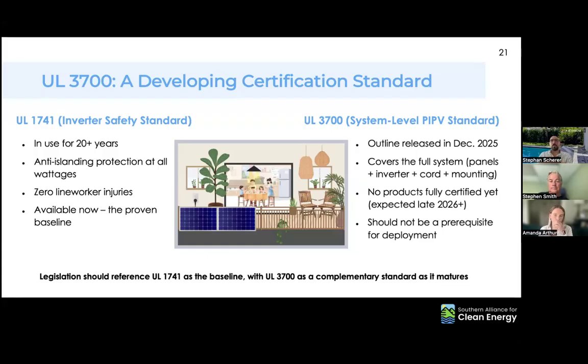In the meantime, as a draft certification, it tries to cover certain topics not covered by previous certifications. We've got UL 1741 for inverter safety, and UL 3741 for breaker masking — all very well-defined testing standards that we can adhere to and test to. UL 3700 also addresses breaker masking, which helps a lot. It also addresses GFCI, requiring a GFCI device that can measure in both directions, or at least one that measures in the opposite direction of the home GFCI already installed. At the moment, it also addresses the actual plug.